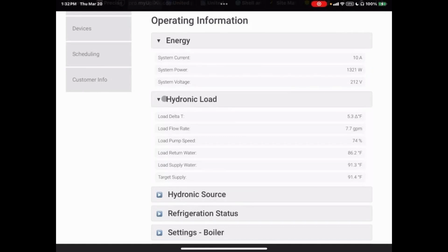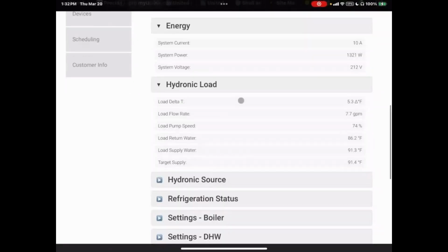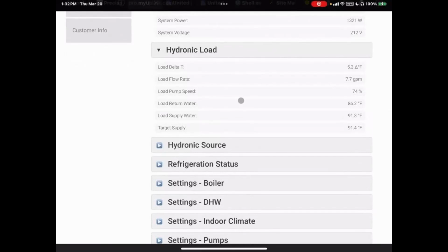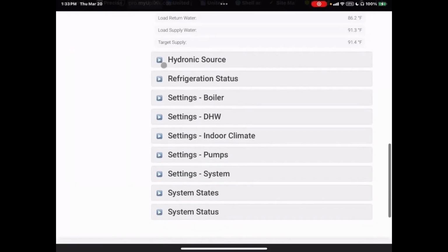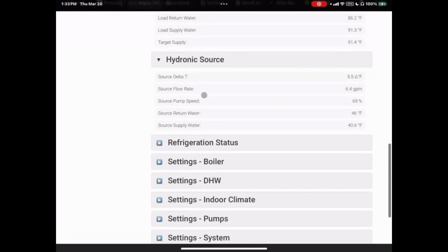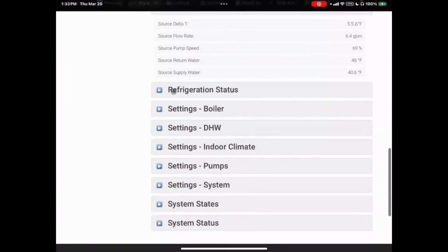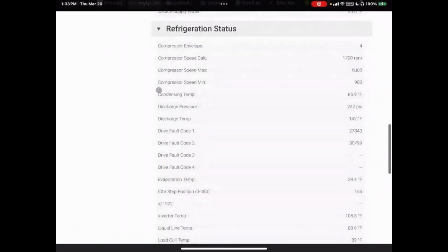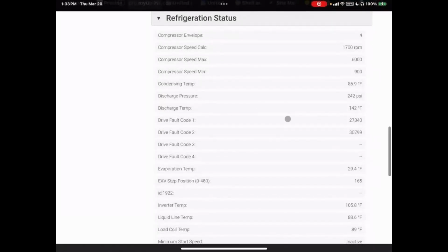But if I want to look at hydronic load, so yes, this heat pump is running right at the moment. We've got a delta T of 5.3, a flow rate of 7.7 GPM, and load pumps at 74%, and we can see our load supply and return water and what our target temp is. Our supply water right now is 91.3, our target supply is 91.4, so I'd say we're doing pretty good on target right there. We have these drop downs for a whole lot of categories. Of course, we can see what the loop temperatures are on the source side. We can look at refrigeration status, and a tremendous amount of information is available here.